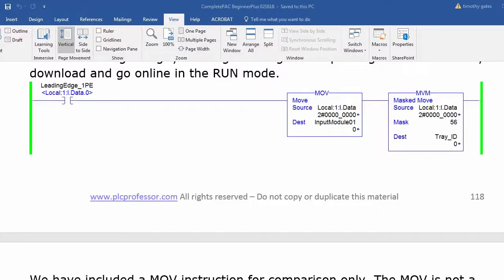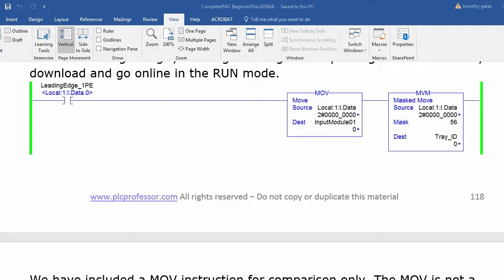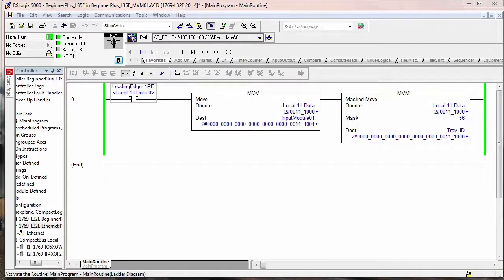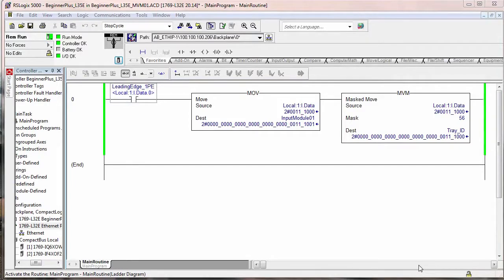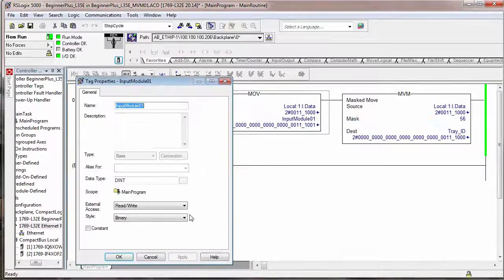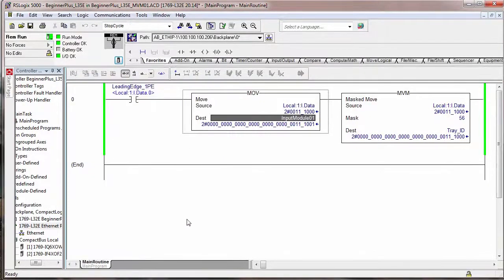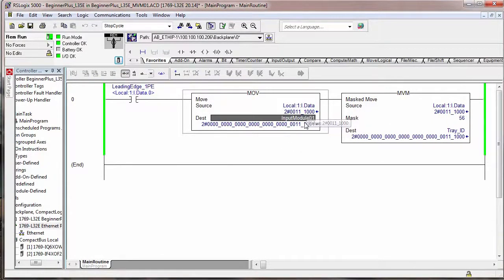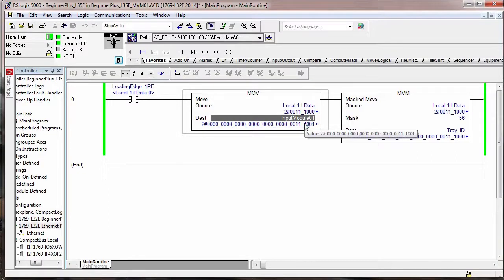This rung of logic that I had you put in your program is real simple. It's got two move instructions, one with a mask and one without. The sole purpose is for you to be able to compare the value in input module 01 with the tray ID. So the move is just a direct move. Basically, you could say that we are buffering the state of the inputs from local 1i data into another tag called input module 01. But primarily, this is there just so you can compare the two values. To make it a little easier, notice that I changed the display configuration for input module one and tray ID. I simply did that by going to edit and then change this from decimal to binary and hit apply.